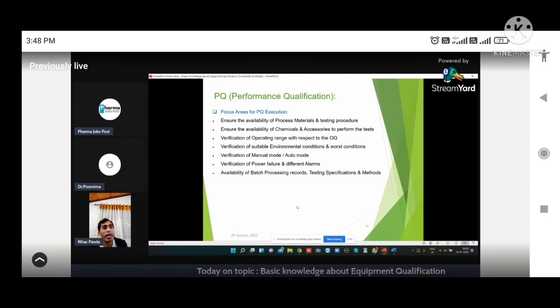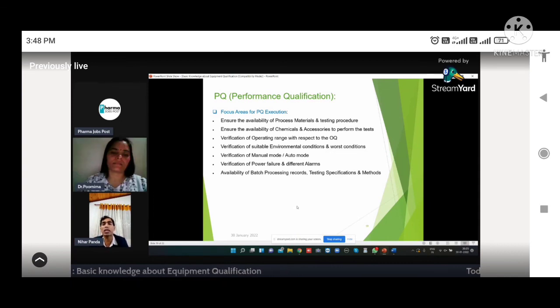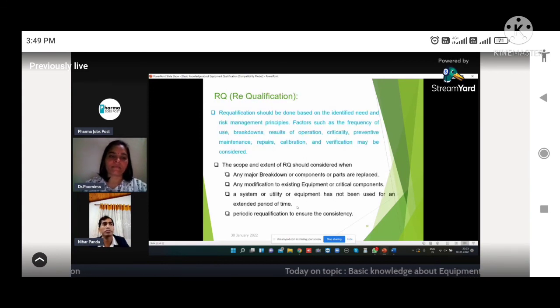Then verification of manual mode and auto mode, whether the equipment is giving the same result with manual mode and auto mode. You have to verify those things also. The same parameters, same batch processing can be done, and parameters can be checked with those process materials. Then verification of power failure and different alarms also. During PQ, those things need to be verified also. Then availability of batch processing records: you have to check before PQ that BMR and BPRs are available, test specifications and test methods, method of analysis, all the things are available. You have to verify all the things.